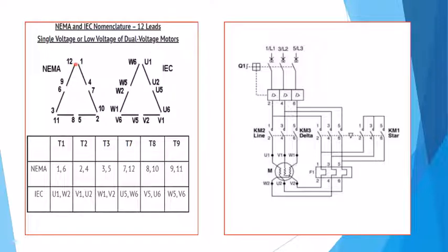Well, if you tie 10, 11, and 12 together, it creates what they call a Y configuration. And what happens then is the actual voltage across this winding ends up being roughly 1.73 times less. So you could provide 480 to the top of the Y, and it would end up giving this part of the winding about 277 volts.